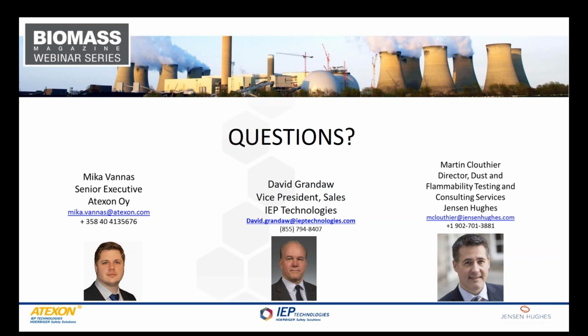Well, this is Martin with Jensen Hughes. Because I'm a fire protection engineer with fire protection experience, I can answer that question. I'm not sure if I heard it correctly, but it sounded like the question was how much accumulation of a dust layer on surfaces in the building can a fire involving that material be controlled by sprinkler protection. And actually, it's not the dust layer that is an issue, it's the overall combustible loading in that facility. So normally you would not consider dust layers as a factor in designing fire protection or sprinkler systems. There are many more hazards in industrial occupancies that pose much more significant fire hazards than dust layers.